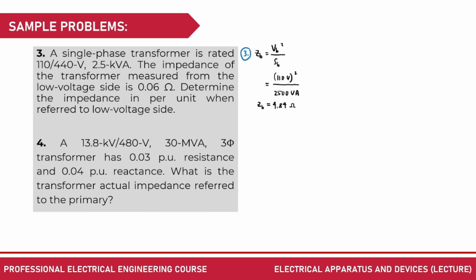Now what's next, after the Z base, we can proceed with taking the per unit. The Z per unit becomes the actual impedance over the Z base. It gives you 0.06 ohm, measured from the low voltage side, over the Z base, which is 4.84 ohms. So we have 0.06 over 4.84, which is 0.0124 in per unit.